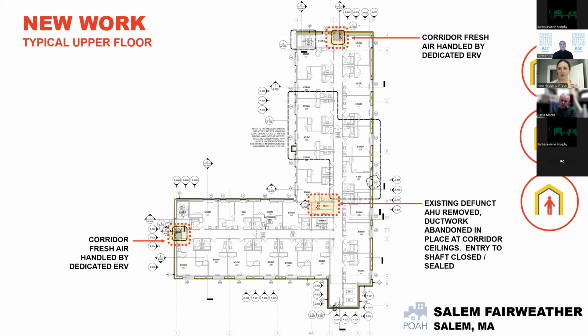So everything we're doing, as you'll see as I continue through how we're handling HVAC, is in response to that major issue - we cannot install and rewire the whole building for a new fire alarm system just because of HVAC upgrades. So we're finding ways around that, and keeping the ERV corridors servicing only the corridors meant they don't need smoke dampers, which became really critical.